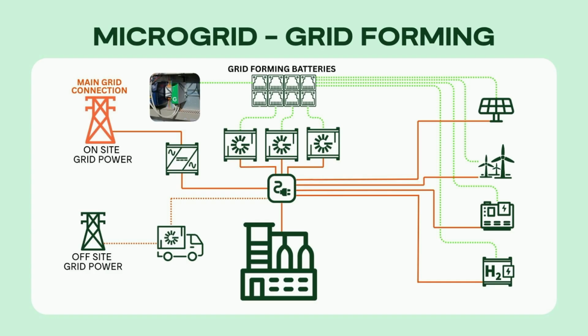1000 amp load, that's out of sync. If anything happens at the load side and it's slightly faster than you expected, we're going to trip that input, that grid connection, and thus lose whatever we are following. Of course, looking at the G99 regulation in that sense, because we're grid following, if the grid did trip, the batteries would have to open their contactors and turn off. And everything needs to switch off.